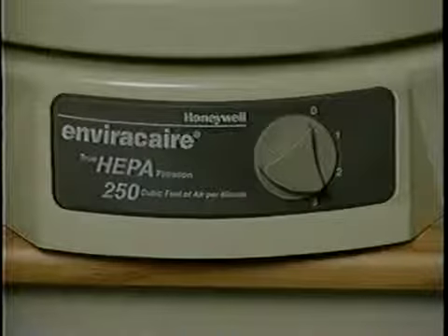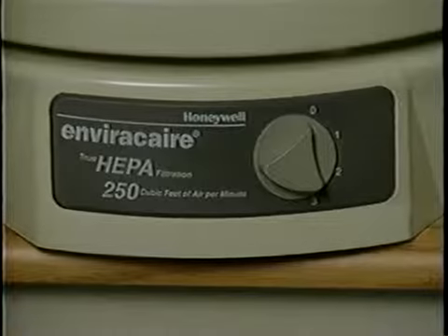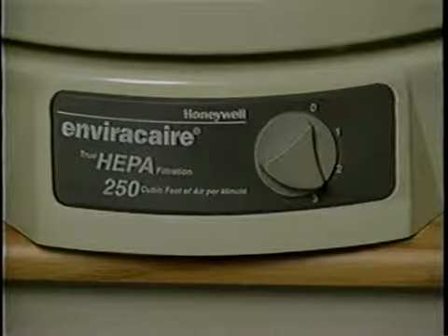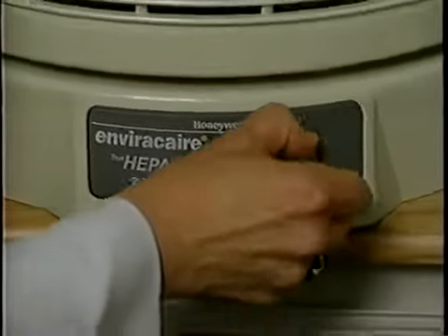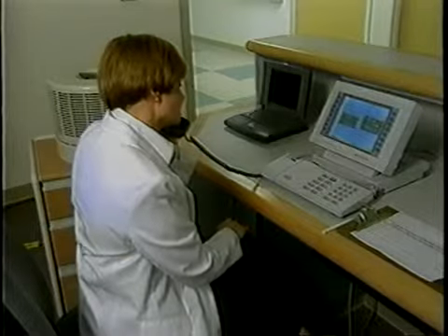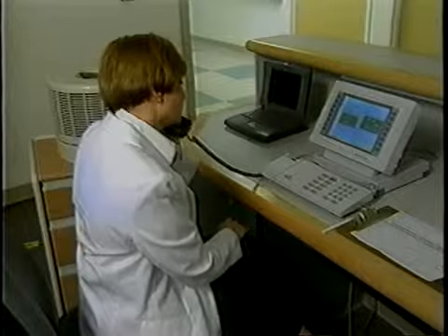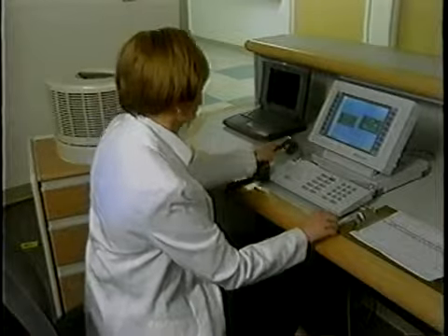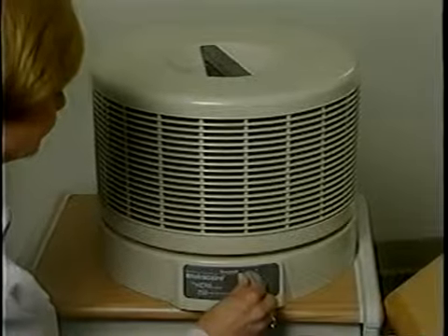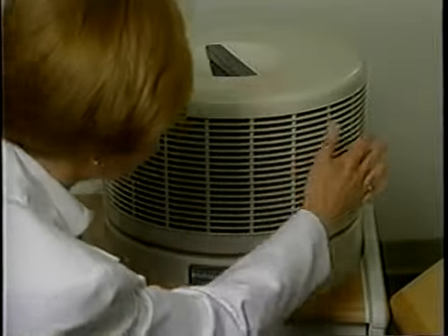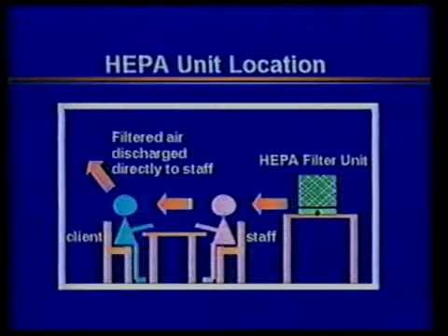We recommend that you size them to produce about 25% more capacity than you want. Also, these units can be noisy, especially at the high fan setting. We recommend that you select them based on the airflow at low or medium speed. Locate the units at an elevation which allows air to be discharged from the unit to the staff at approximately head or breathing level. The discharge can be determined by moving your hand around the unit until you feel the air. When properly located, the staff should feel gentle air movement.